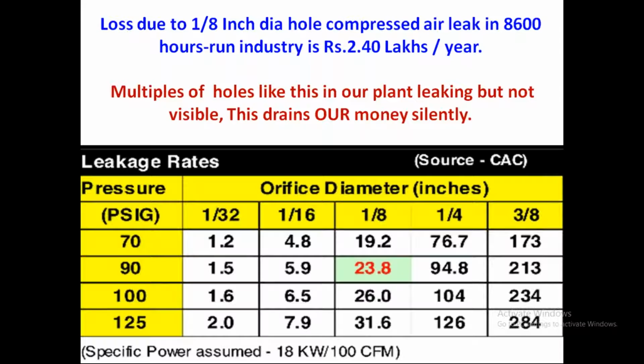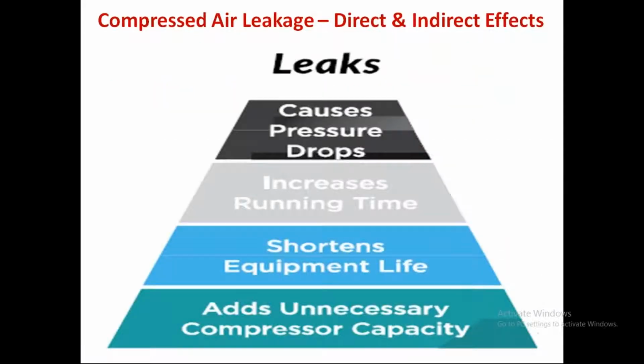In one industry in Madhya Pradesh, they put a blackboard at the compressor user point: we are losing around 10,000 rupees per day because of compressed air leaks. It is an input to the user to see that leaks are arrested. The air gets silently drained out. Leaks can cause pressure drops in the compressed air header, increase the running time of the compressor, or shorten the equipment life of the compressor.